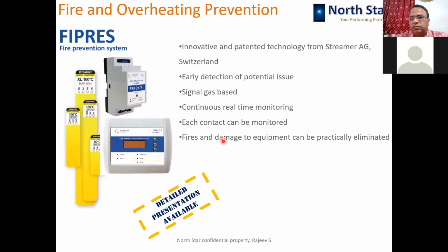Okay. The fourth solution which we provide is FIPRES, which is for electrical panels where, because of poor contact, because of overheating, a lot of damage happens, fire happens. So this system detects such probable points where the fire can start because of deterioration in the contact resistance. So it detects that resistance much early.